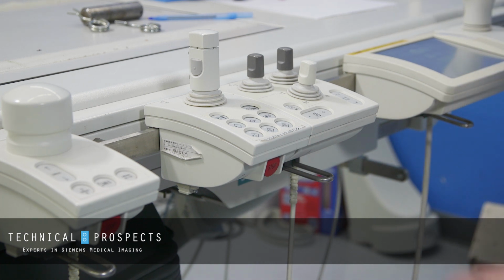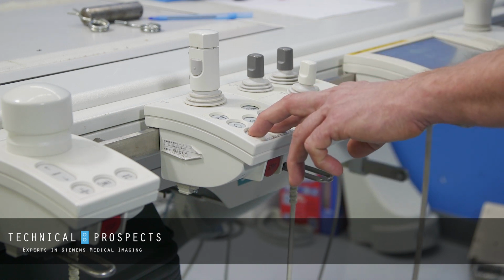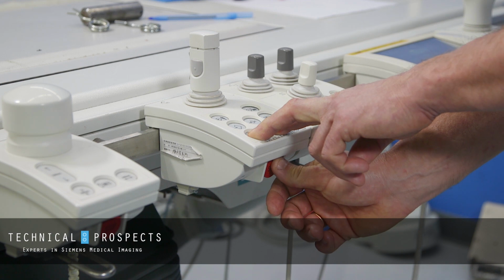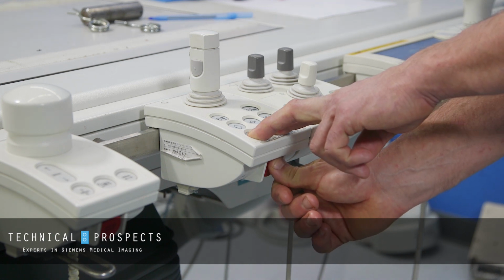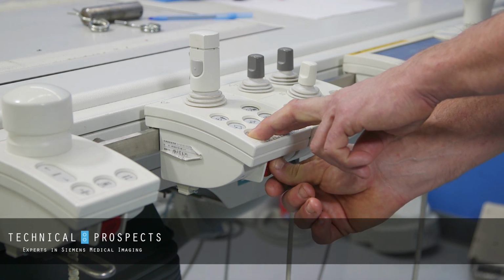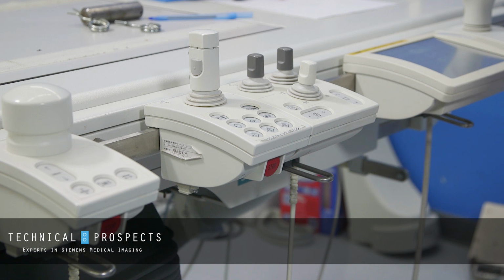be performed by simply pressing program 1 and program 2 in the stand control module and pressing the emergency button underneath. You hear some clicks happening, you release the emergency switch, remove your fingers from program 1 and program 2, and after 10-15 seconds you will hear the brakes coming back, and that means the system is ready for the normal operation again.